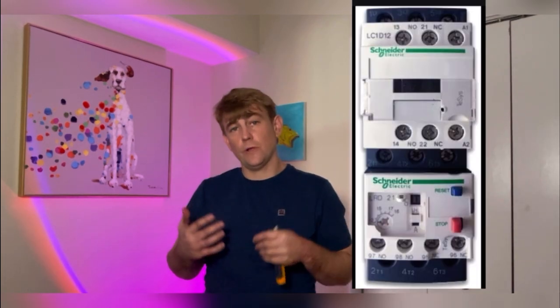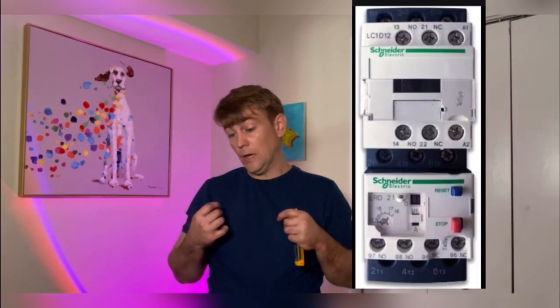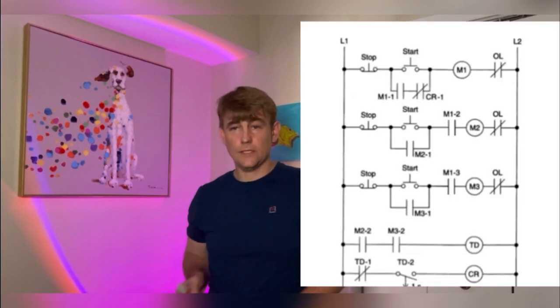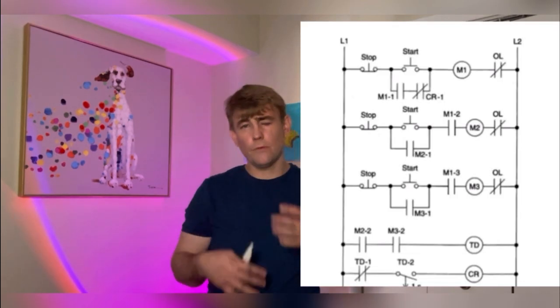Starters have overloads on them. So if a motor fails electrically, or if the pump gets clogged up and it can't move, or maybe you blow one fuse and you're single phasing, the amperage is going to shoot up, and higher amperage means more heat. Those overload units will actually heat up, and they will pop open. Your overload will trip. If the overload fails, then your fuse will pop. If your fuse fails, then your circuit breaker will pop. So generally in industry, you'll see that same exact schematic over and over again. You see it in motor controls. You see it in this stuff. Again, that's for more rudimentary systems.